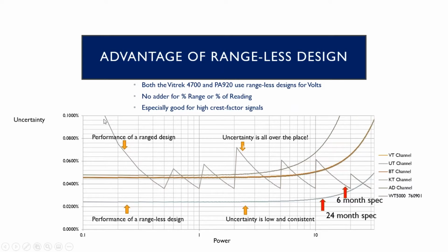You start off with low power and the uncertainty is bad, but as the power goes up, your uncertainty gets better and better. Then all of a sudden you have to range, and your uncertainty gets worse again, then you add more power and it gets better. This is a typical sawtooth pattern—you see it quite often on anything that ranges, meters or signal generators.